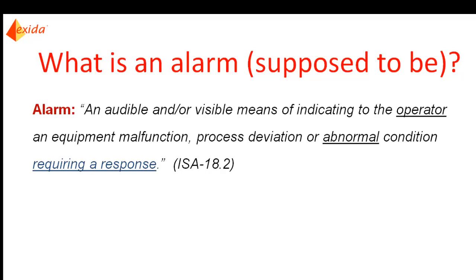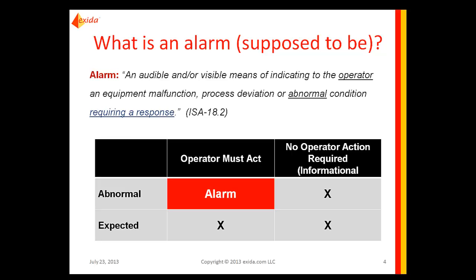If the operator does not need to perform a corrective action, like opening a valve or turning on a pump, then the point should not be an alarm. Alarm overload and nuisance alarms are oftentimes caused by alarms that don't really meet the criteria — they don't represent an abnormal condition or require the operator to take an action. The purpose of alarm rationalization is to ensure that each alarm meets the criteria as defined in ISA 18.2 and in your alarm philosophy document.